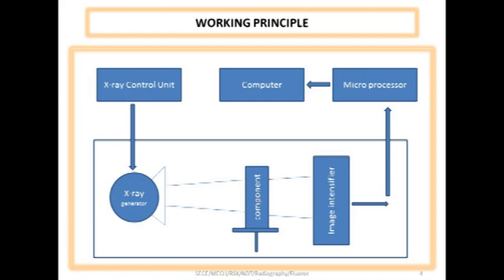Once the x-ray passes through the component, it is made to fall on image intensifier. This image intensifier is nothing but a fluorescent material which gets activated by the strength of x-rays passing through the component. Finally, from the image intensifier, the signals are processed to the microprocessor.